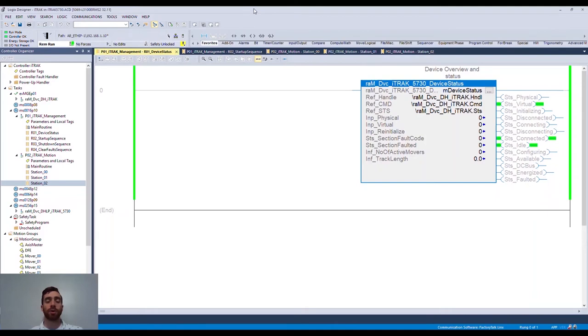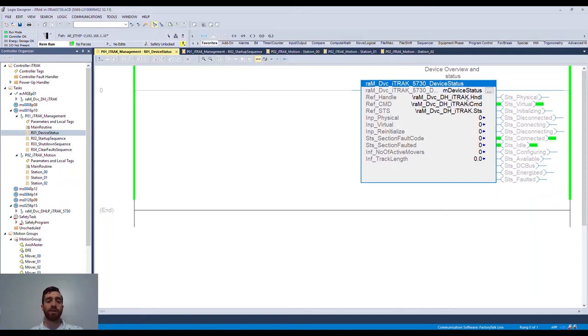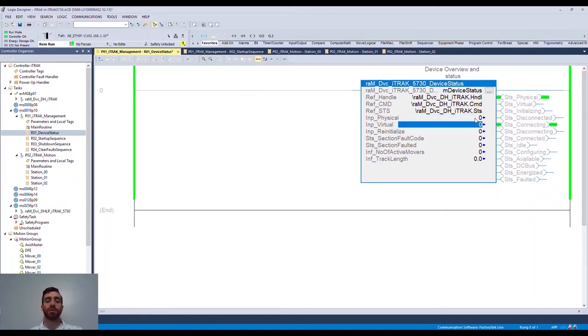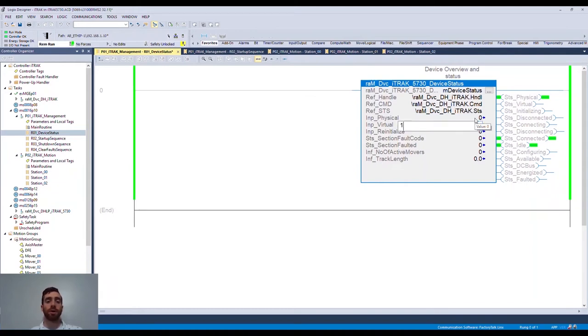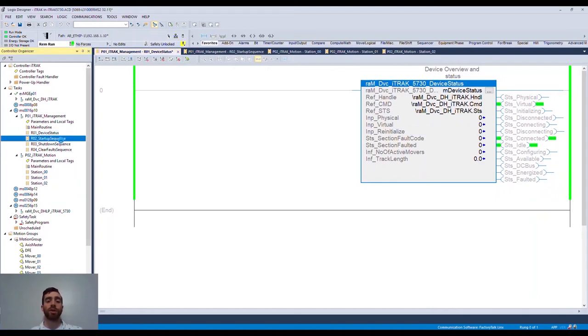I've already downloaded the program into my controller. You'll notice that there is an easy AOI that acts as a faceplate for the iTRAK. It defaults in the virtual configuration. Notice that by triggering the virtual or physical bits, you can quickly switch over to a physical system or back to a virtual for testing and development.